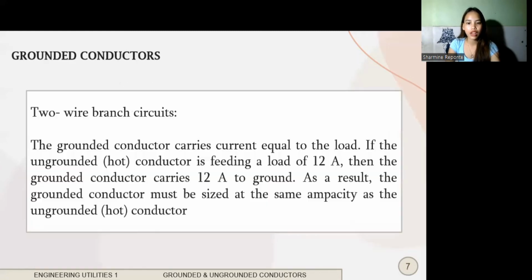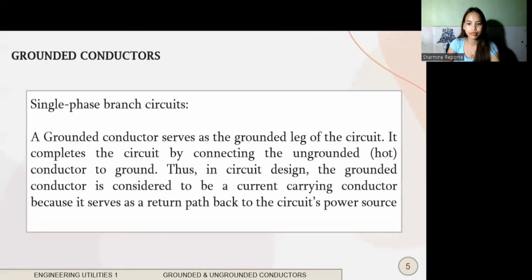Grounded conductors. A grounded conductor is a system or circuit conductor that is intentionally grounded or attached to earth. Grounded conductors provide a safe path for ground fault current to flow. Simply said, a grounded conductor is a conductor that is connected to the earth. As I said earlier, grounding provides an alternative way for the faulty current to flow back to the ground or source so it does not cause shock or worse. So, grounded conductors are used as a path for the faulty current to flow.